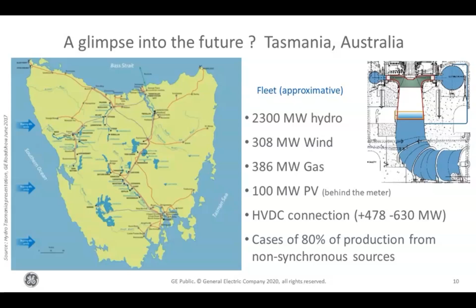They've got the hydro, and also a fleet of about 50 hydro units, of which 14 are able to spin in air and provide a synchronous condenser function. So to ensure that 80% inverter-based generation allows the grid to stand up, they're using all the hydro machines that can provide reactive power. The benefit is that when you no longer need the reactive power, those hydro units can generate energy as well.